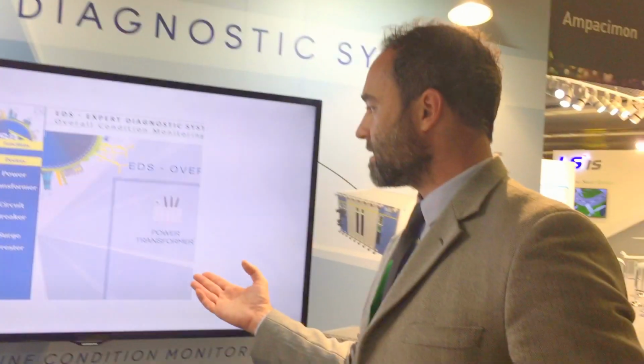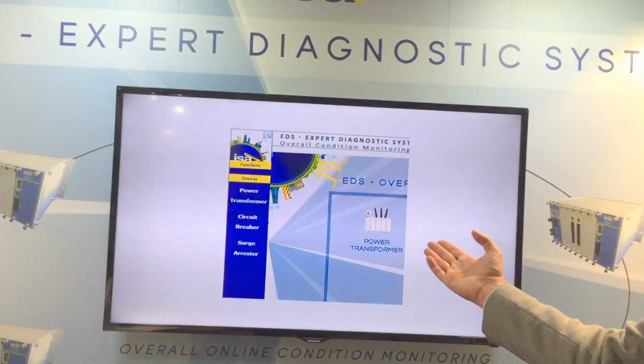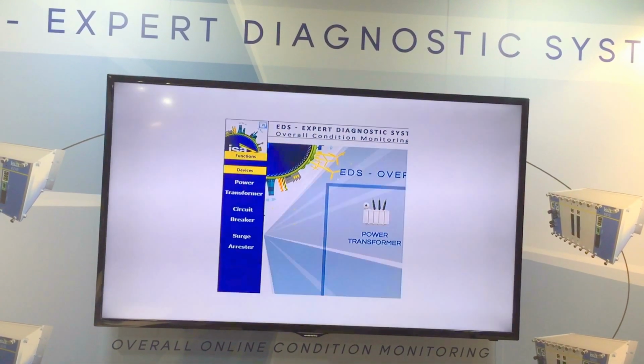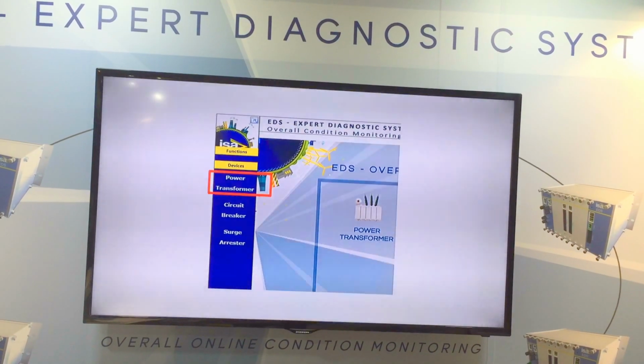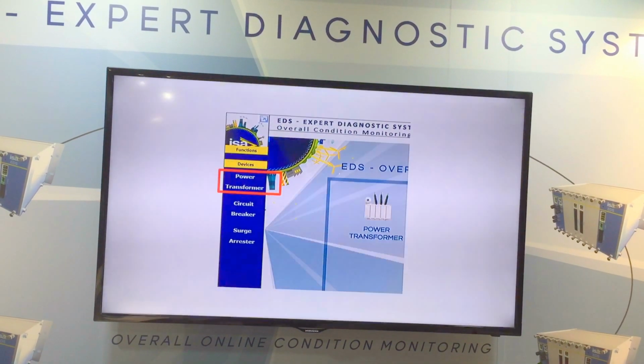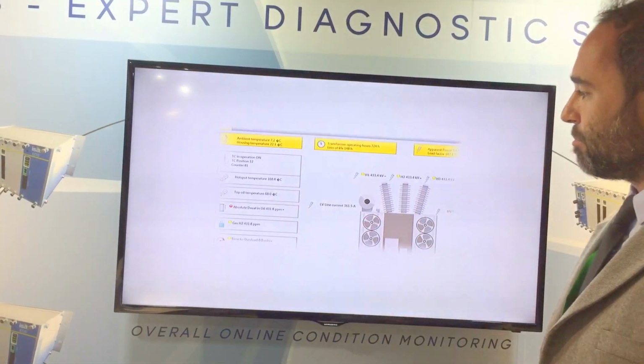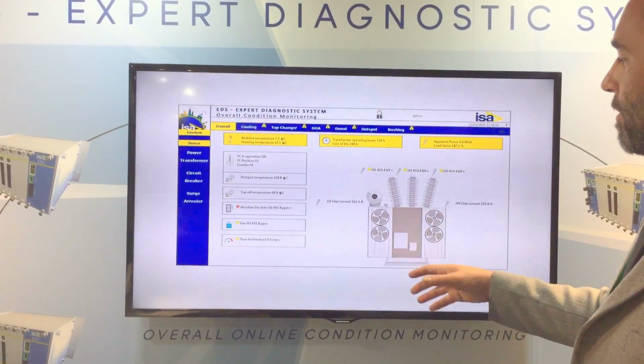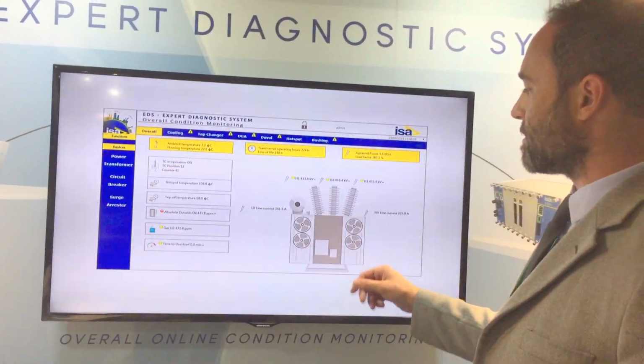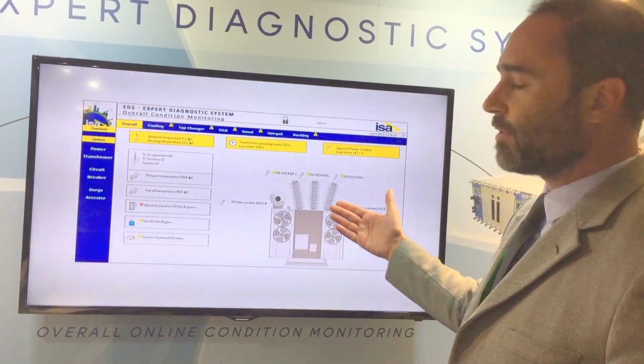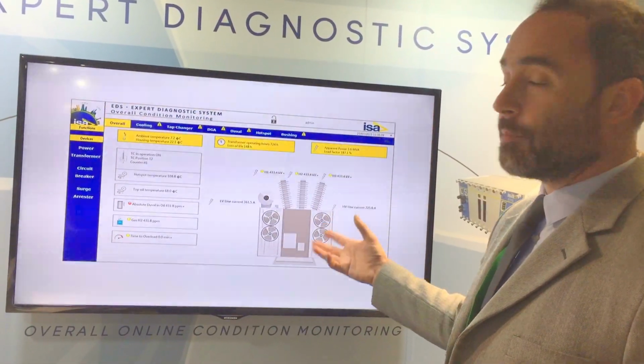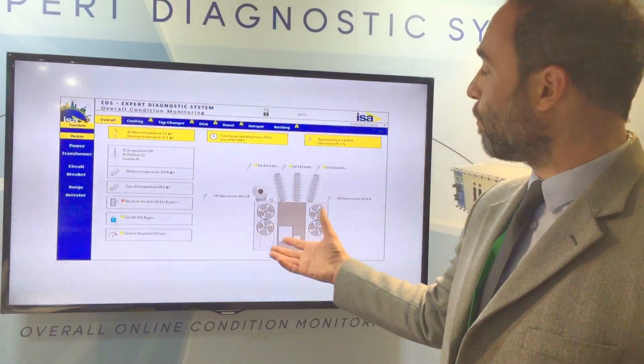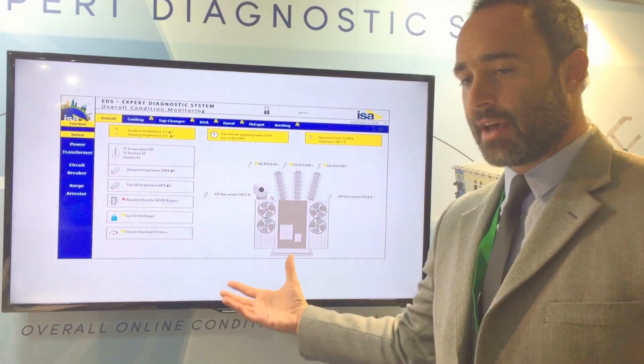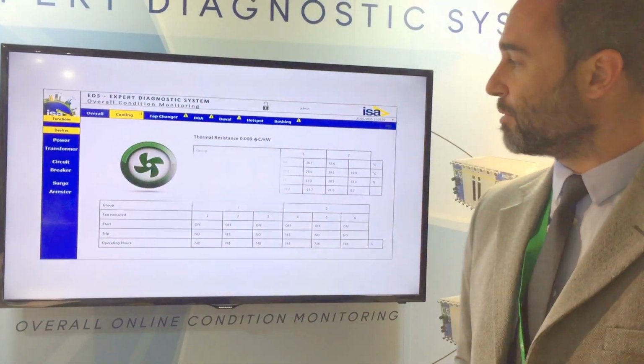So the EDS, as you can see, has a very cute application. It's a web application where you can see the state of your assets as we said, power transformer, and on a power transformer you get to see many parameters from input and output, current, voltage, of course, temperature, dissolved gas analysis, water, and also we have a plan to have a partial discharge and tan delta to be monitored constantly.